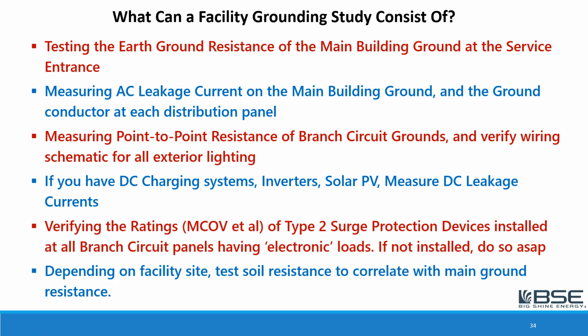And then this is not part of a grounding survey per se, but we think it's important to do. And that is to check the ratings, which can include the maximum continuous operating voltage, and there's several other ratings that should be checked, of the type 2 surge protection devices, which are installed on all branch circuit panels having electronic loads. And if you don't have type 2 surge protection, we recommend putting it in. It's really important.